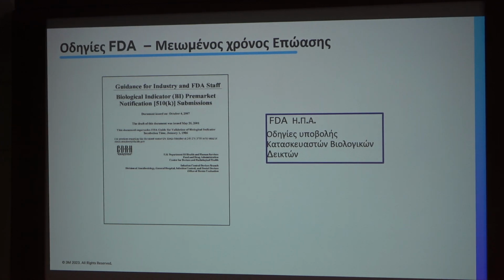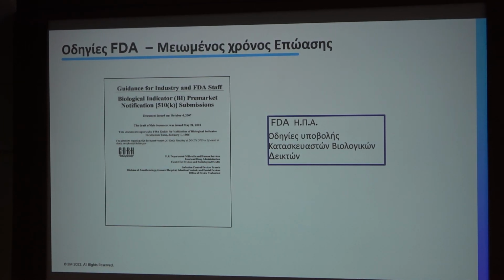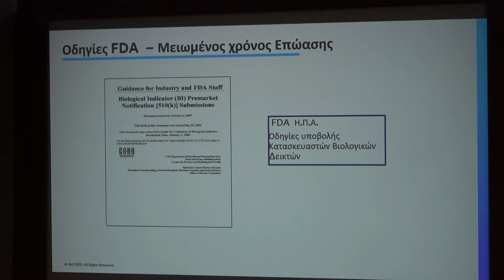And it's not enough, because I have mentioned that there is another protocol about these reduced times. So FDA has a protocol, and you have to comply with it in order to show that you are giving results in a shorter time. So I put an example here, because when something is FDA approved, there shouldn't be only a letter given by FDA saying that yes, this is the product. There should be something else like a report.